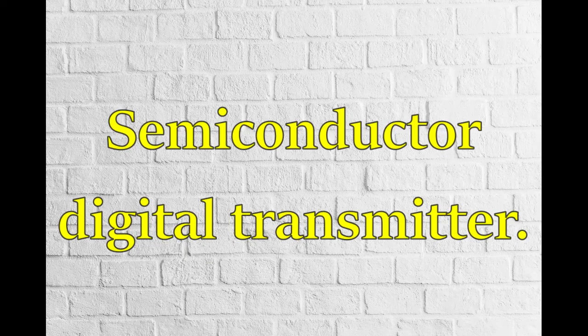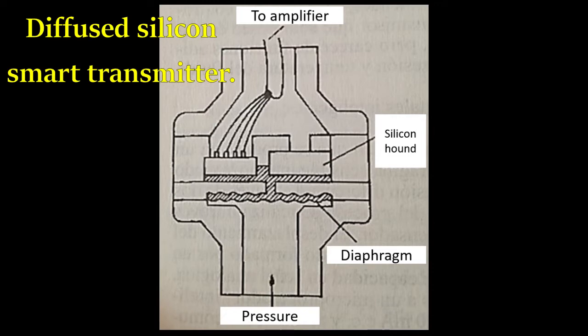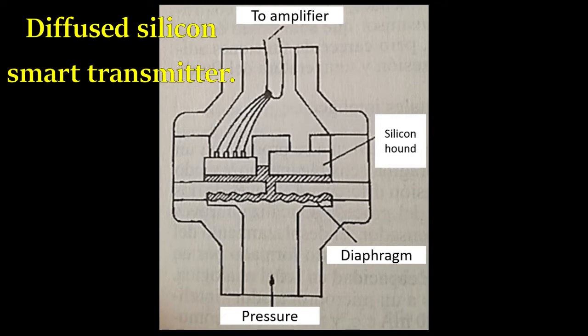The second model is based on semiconductors: when subjected to pressure, they produce an electric current, which is used in this transmitter model. For example, in the diffused silicon smart transmitter, a diffused semiconductor made with a thin silicon layer doped with certain techniques is used to generate a stress-sensitive zone.